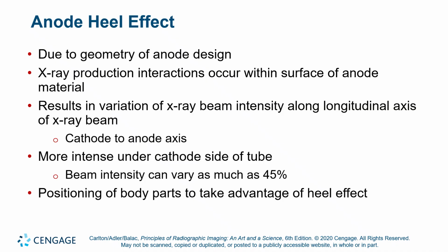And so you can get an intensity variation of about a 45% swing, where the anode beam is thinner by about 45%. So let's say we had 100 photons per square centimeter coming out of the cathode side, you would only have 55 photons per square centimeter coming out of the anode side. Okay? This is called the anode heel effect.